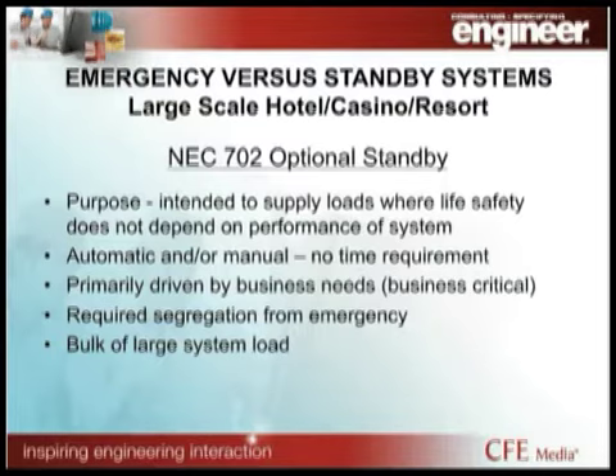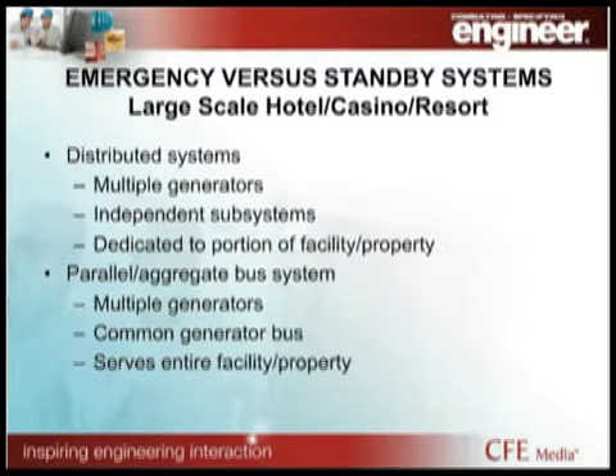It can be automatic and or manual. There's really no time requirement. And again, primarily driven by business needs. And internationally in Dubai, Hong Kong, external to the U.S., they typically refer to this system as business critical. It's got to be segregated from emergency. It can be intermingled with your 701 loads, but it cannot be intermingled with 700. This is going to be the bulk of a large system load. It's going to be those things that the owner wants to make sure they can maintain operations in the event of a power outage.